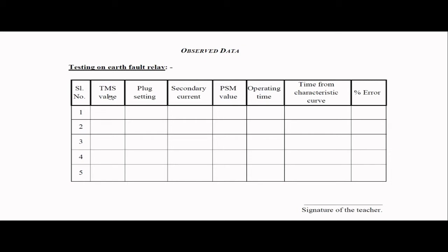First is the time setting multiplier value. As I mentioned, the relay operating time can be controlled by a dial put on the relay, which is called the time setting multiplier dial. The dial value is from 0.1 to 1.0. So according to the requirement, you set the dial. So this is the time setting multiplier value.